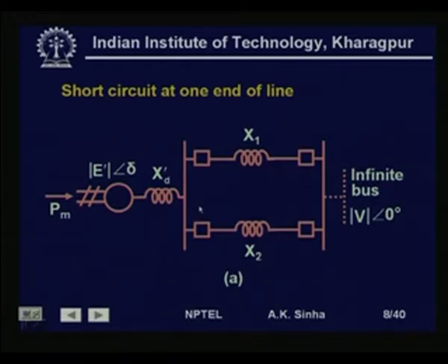And this operation we call the recloser of the circuit breaker. Now, if a fault has occurred on this line, let us say, and we have opened the circuit breaker, then we have only one line left. But after some time, if we reclose and the fault has been cleared, then both circuits will be on, and so the power angle characteristic will change to the pre-fault condition. However, this recloser has certain disadvantages also.